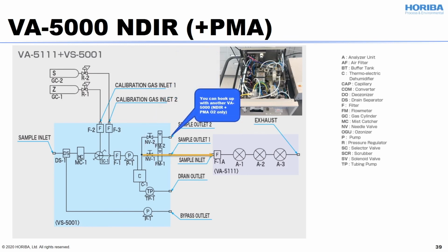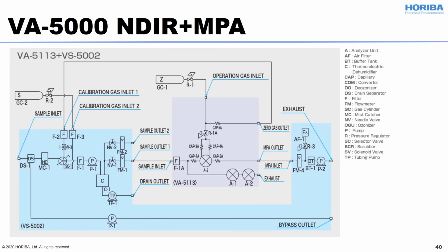And you can hook up with another VA-5000 by hooking up with the sample outlet 2. And the drain comes out from the cooler and to the drain outlet. This is the different flow schematics, sample unit with the MPA. Like I said, MPA has two pumps. One is pushing and the other one is pulling. By using two different types of pump, we are maintaining the proper pressure in the flow.